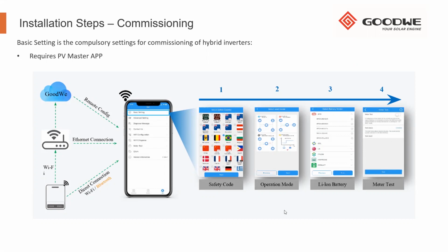I won't go too in depth into work modes since Warren has covered this for us. Thereafter, we go to select our battery modules. One thing that you'll know in the battery module selection: should there be a battery that is on our compatibility list and you do not see it in this list, that just means that your inverter's firmware will most likely need to be updated for it to appear, because the inverter firmware does give through what is displayed in the app.